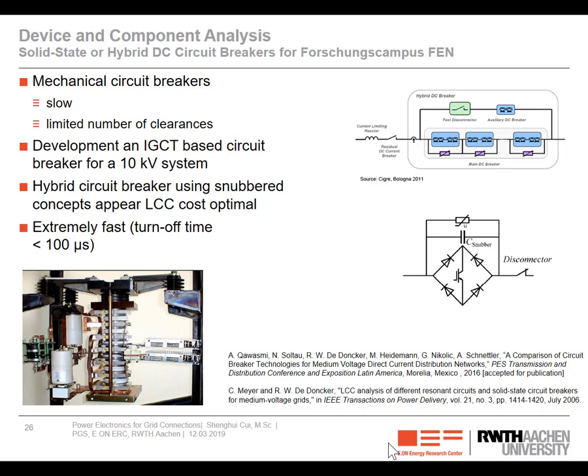So for DC, if we look at the mechanical circuit breakers, they are very slow, and they have a very limited number of operations. And compared to the AC, we know in DC grid, the fault current develops way faster. So such slow mechanical circuit breakers, we can say are almost useless. So we have to look into the solid state solutions.